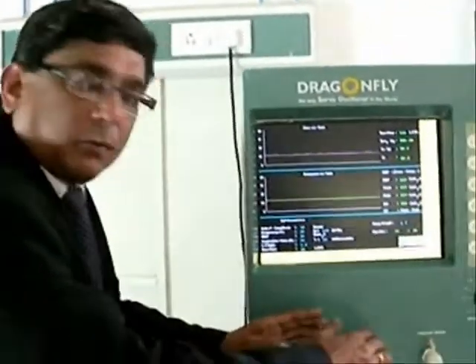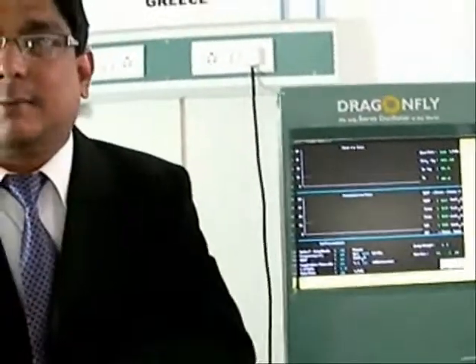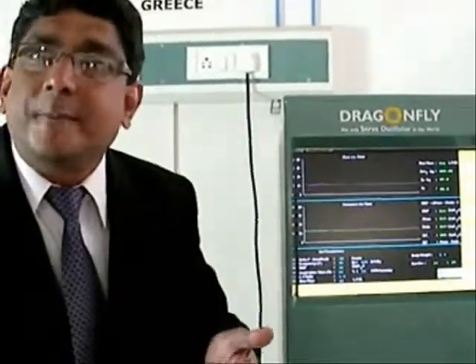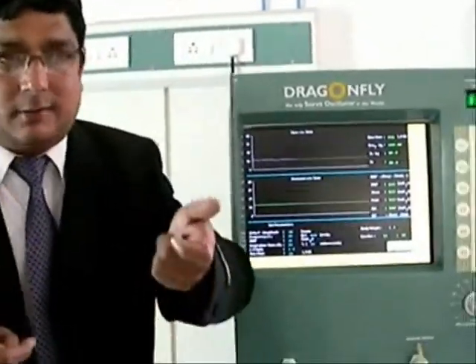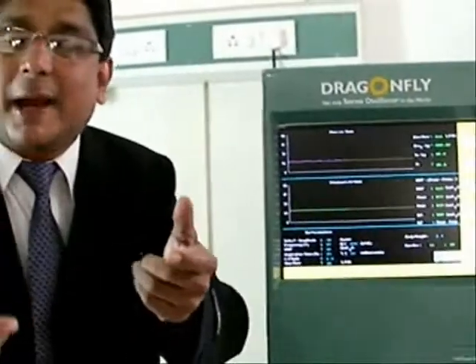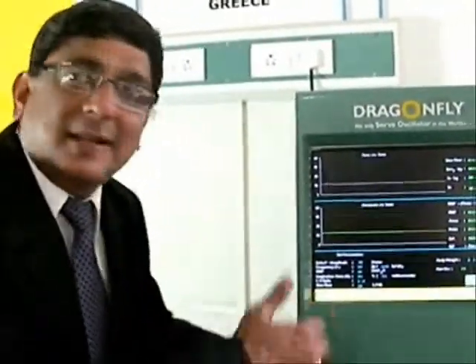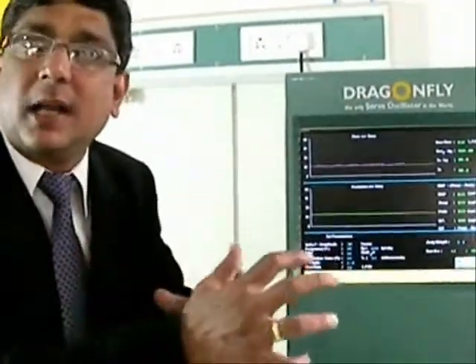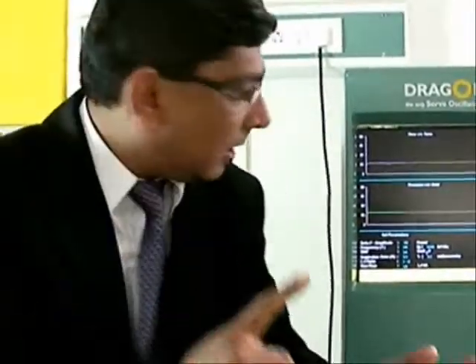So what we call the handshaking mechanism: if you increase the pressure, automatically a signal is also given to the flow, and the flow automatically adjusts. As I've explained, there are microcontrollers in it, so they talk to each other in their language and adjust and open the orifices accordingly, ensuring that whatever pressure is set by the clinician is maintained, irrespective of whether you change the amplitude, the inspiration time, the delta P, or so.